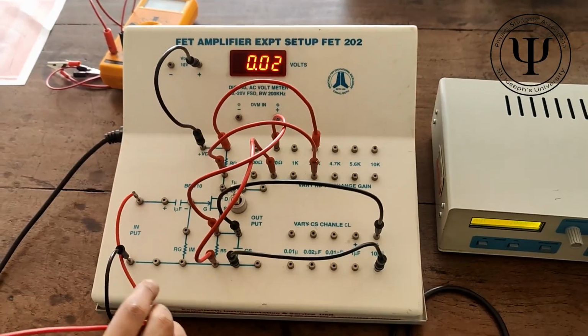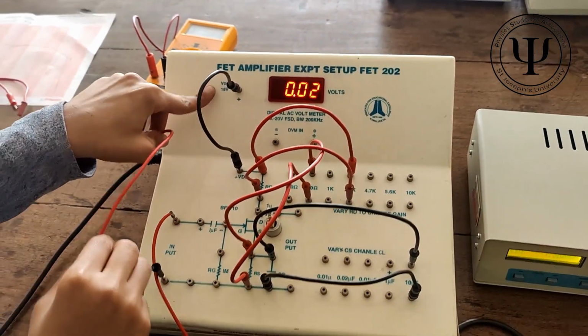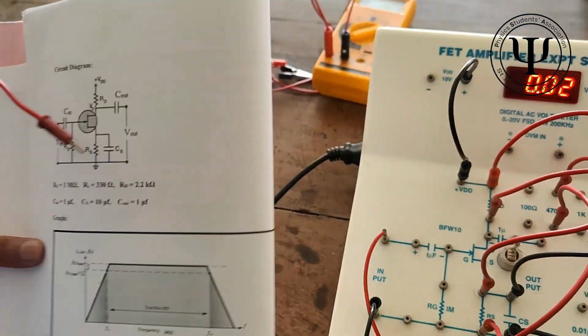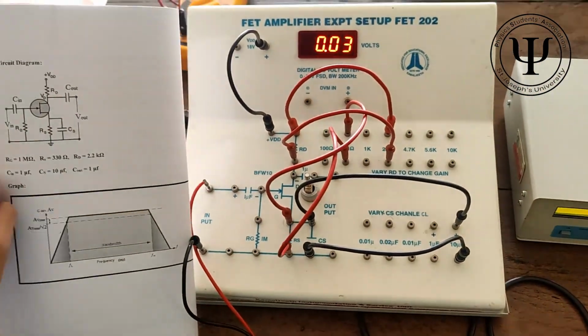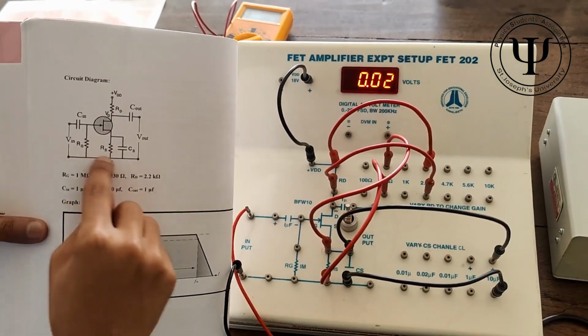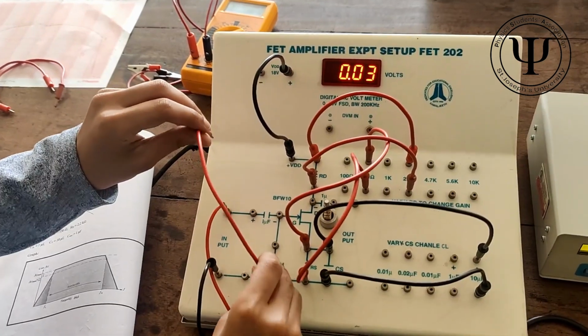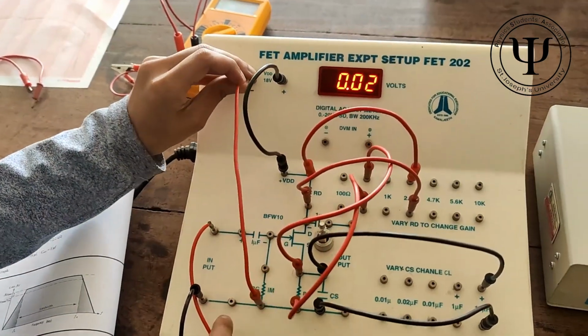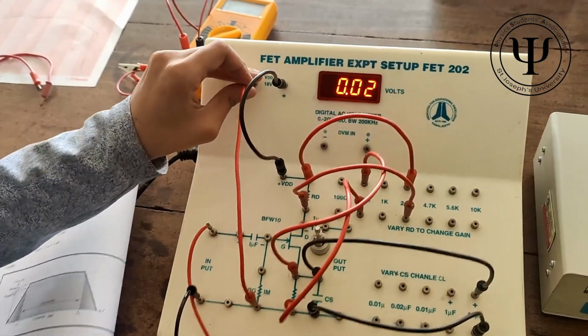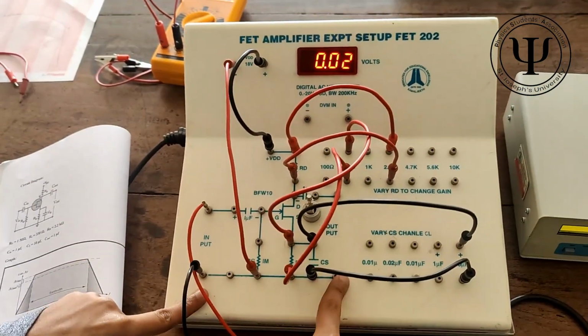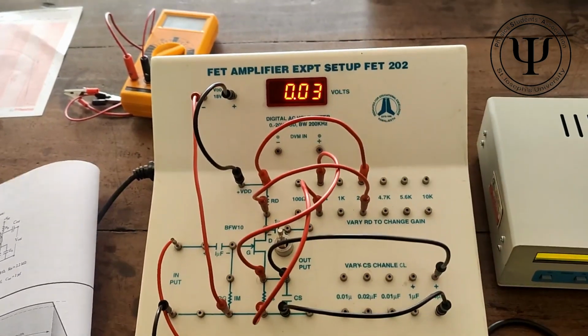And up next, we're going to take this one and connect it to the ground terminal, which is going to be here. Now since RS is already connected, you can choose to connect it here or here because they are all shorted, so that doesn't really matter. You can connect it either here, or you could have connected it here too, and that would be perfectly fine too. Basically all these terminals are grounded. They're all shorted together. You could connect it here too, but that's besides the point.